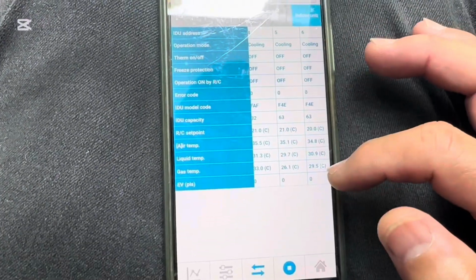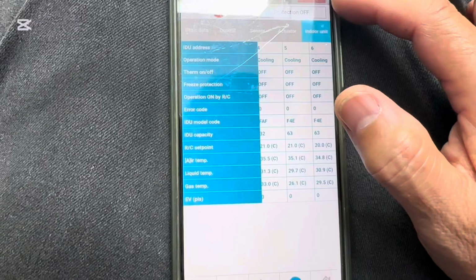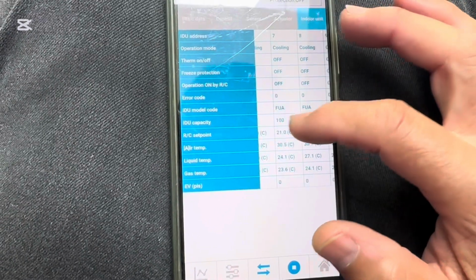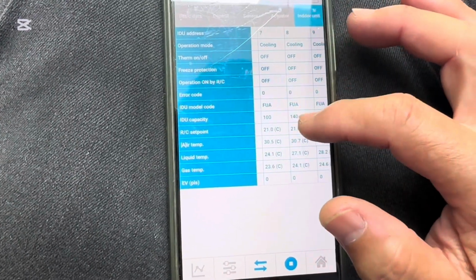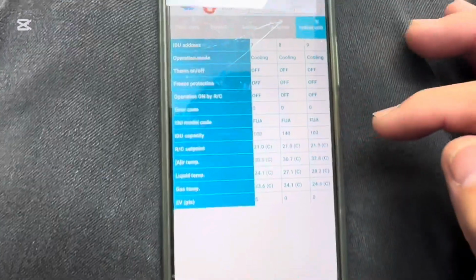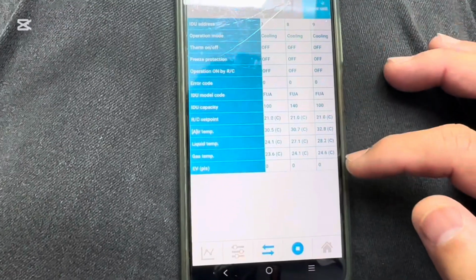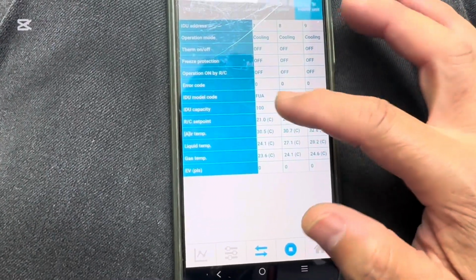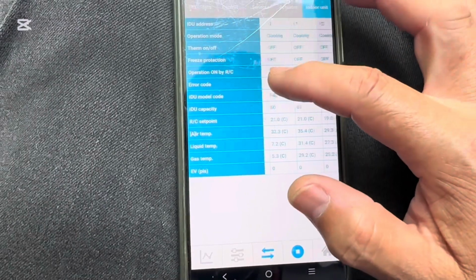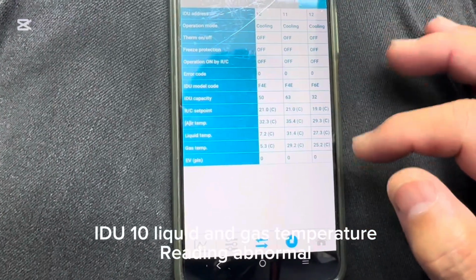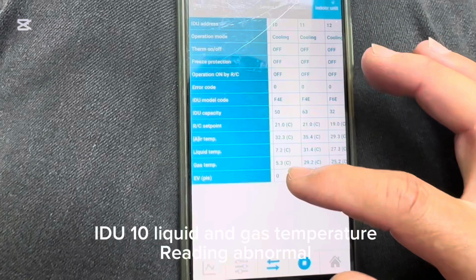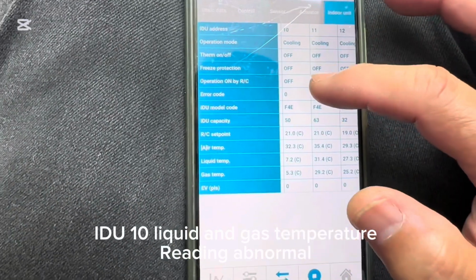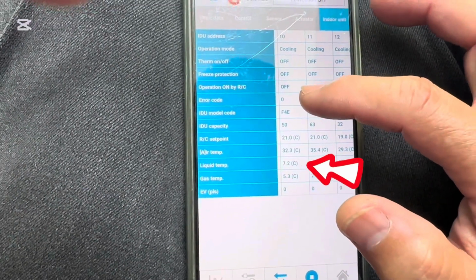1, 2, 3, 4, 5, 6. Okay, temperature okay. We check the liquid pipe and gas pipe temperature, important for the F4 error code. 7, 8, 9, okay. 10, 11, 12, yes. Number 10 got a problem, the aircon is off actually. Okay, aircon is off.